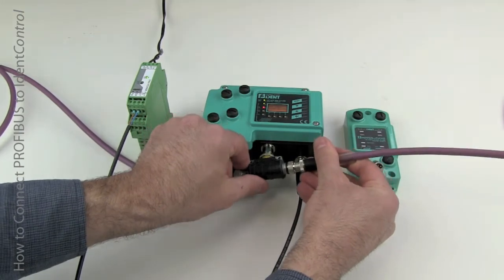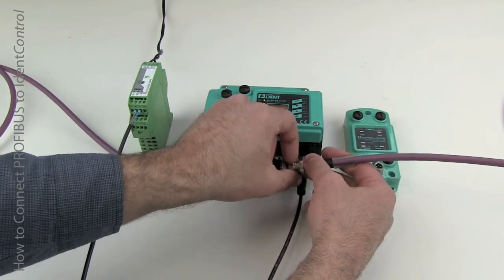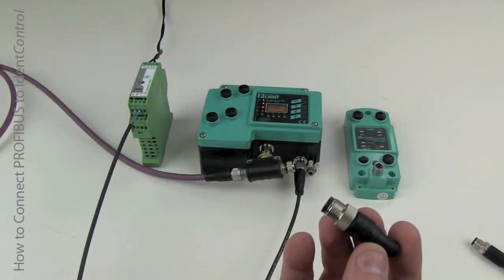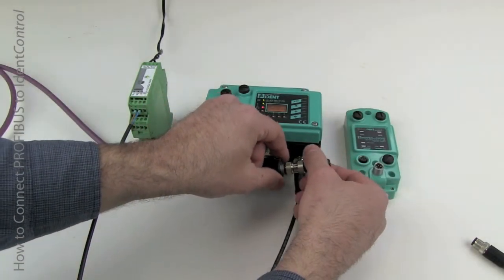If, for some reason, this is the last node of the network, you would, of course, not have the Profibus out connection. Replace that with a termination resistor that you can, in this case, connect directly to the T.